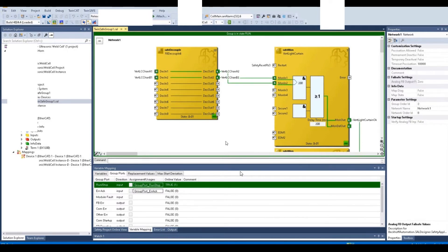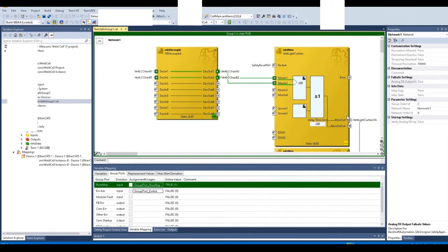This is the light curtain signal — we have two channels. If I break the light curtain, we can see the right-side vertical light curtain OK signal drop. We can see that without the reset signal, even if the light curtain two channels turn on, this output vertical light curtain OK signal will not turn on. After we hit the reset signal — usually that is a push button near the light curtain — once we get the reset signal from 0 to on and then from on to 0, this signal change will make the light curtain output recover to on.